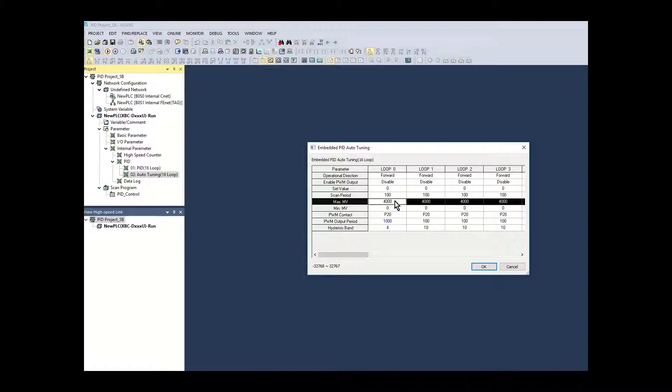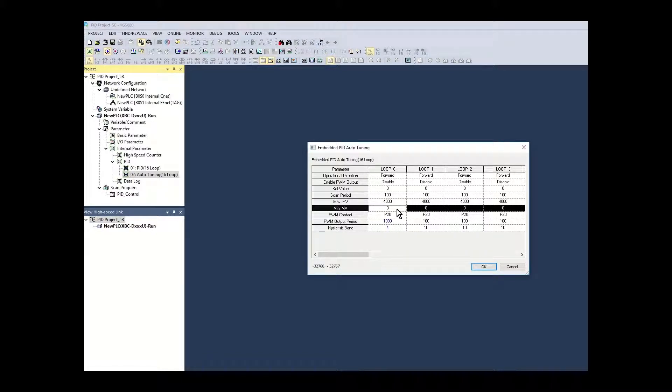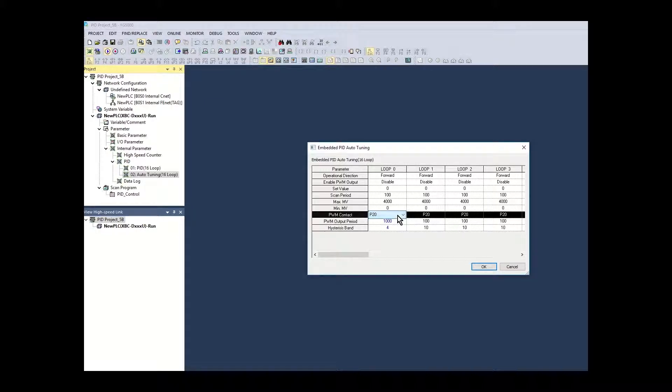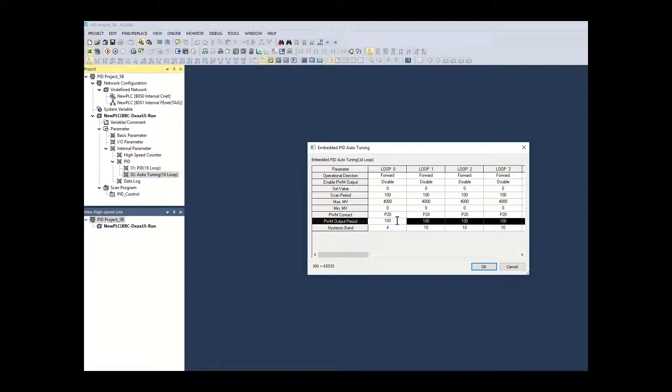The MV max and min values set the range the MV can output. They are left at the total range of the PID control loop. The PWM contact is left at default as PWM MV output has been disabled. The PWM output period is left at default. It is not used in the PID loop in this configuration.